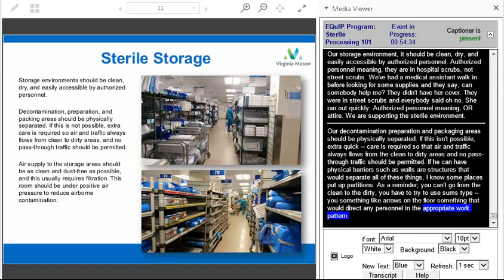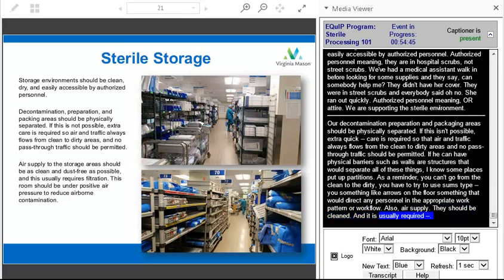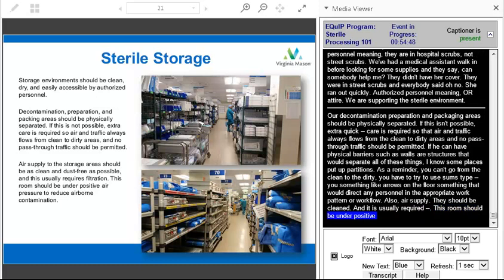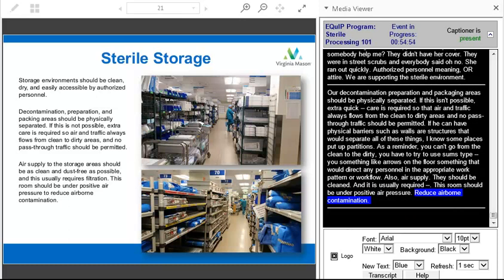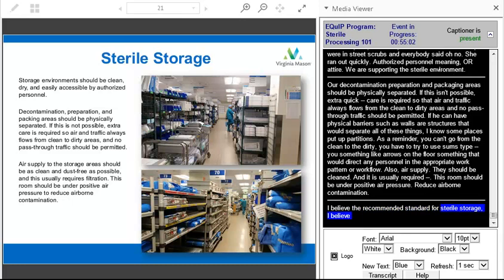Air supply to the storage areas should be clean and dust-free as possible, which usually requires filtration. This room should be under positive air pressure to reduce airborne contamination. The recommended standard for sterile storage is about 75 degrees Fahrenheit, 24 degrees centigrade, and it should not exceed 70% humidity.